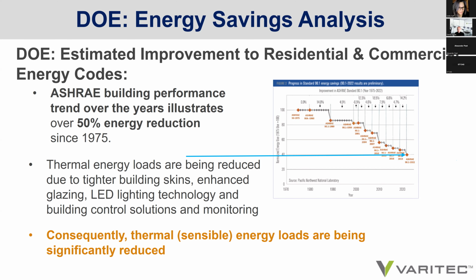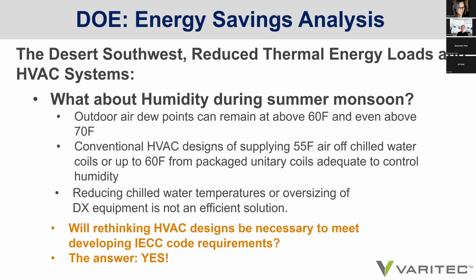But it begs the question whether or not our humidity loads can be maintained as buildings become more efficient and airflows are being reduced. And we should ask the question whether or not 55 degrees off of cooling coils for chilled water systems, or up to 60 degrees off of DX packaged unitary units, are sufficient to maintain humidity control in our buildings. And the answer is probably not.